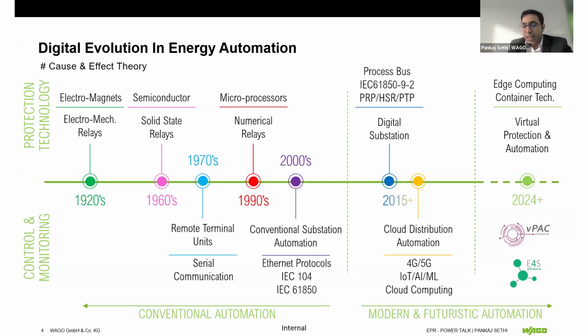Now I call that a conventional system, though it wasn't considered so five or six years back. We call it conventional now because from 2015 onward, we see modern and futuristic automation coming in, which is more data-driven and data-processing oriented. By 2015, the IEC 61850 protocol further evolved to get 9-2, which is process bus, with Ethernet technology getting more advanced through PRP, HSR, and PTP protocols, and cloud technology becoming more prevalent with IoT, AI, and machine learning coming in.